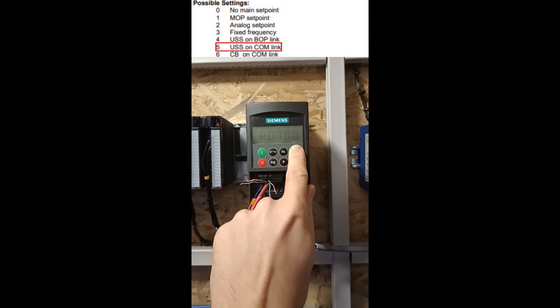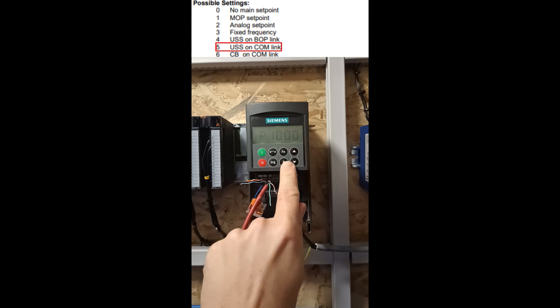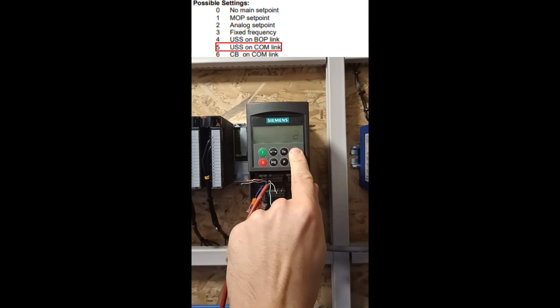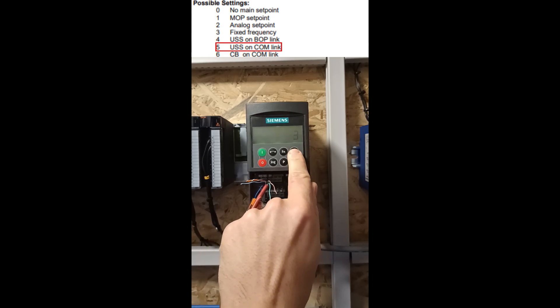And change parameter 1000 to 5 too. This parameter will change the frequency setpoint to USS com link.